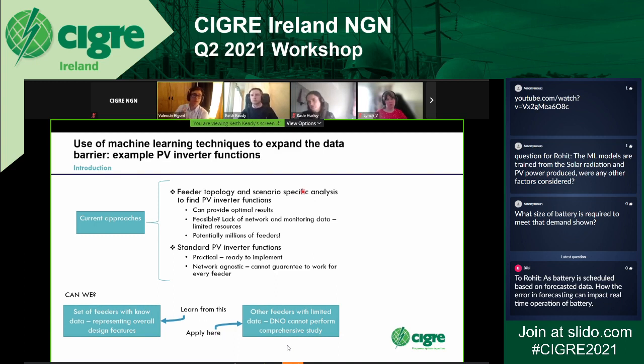So if the inverter sees that the voltage is going up, it consumes more reactive power, or it makes the power factor smaller. And if it sees that the voltage is not as high, then the power factor can be closer to 1. The problem with this is, how do you define the values of those functions? Because once you have them, it's super simple. You go to the inverter, you put it to work, you don't need any telemetry system. There are two ways that people are calculating them.